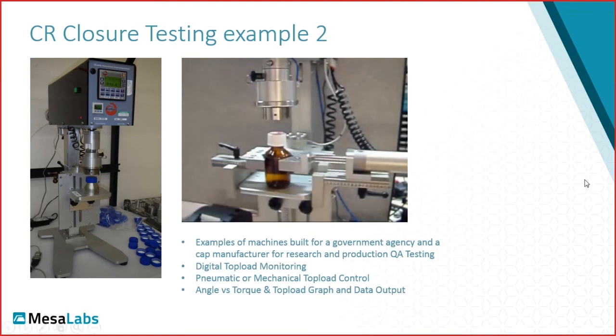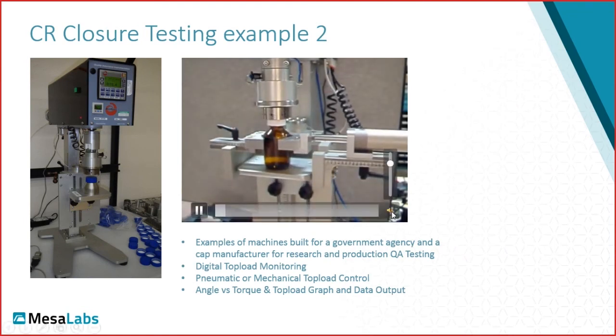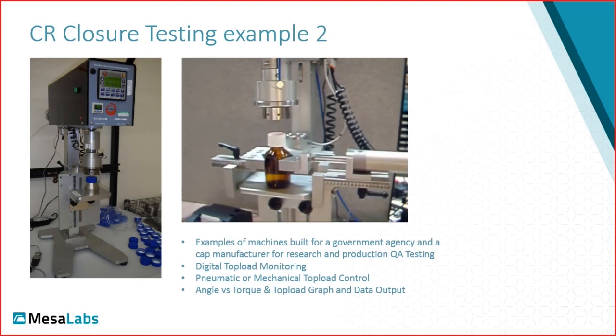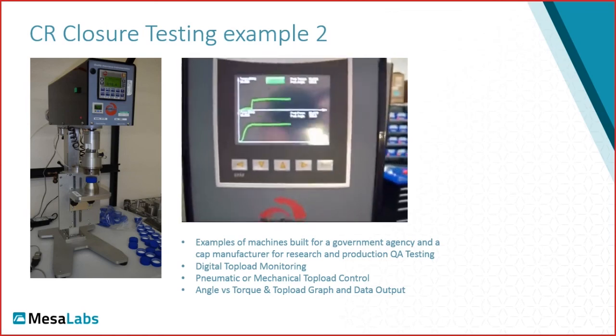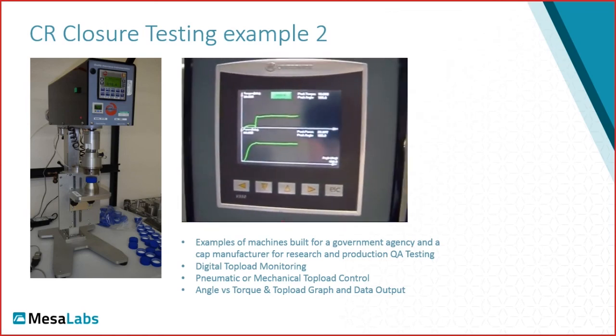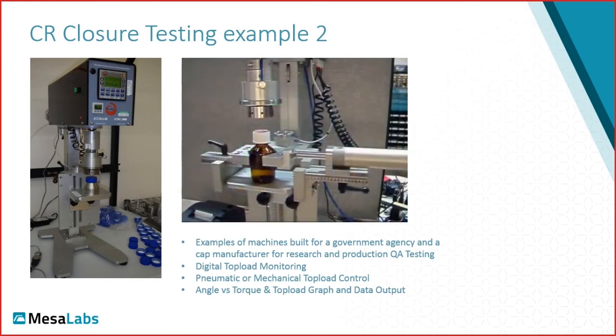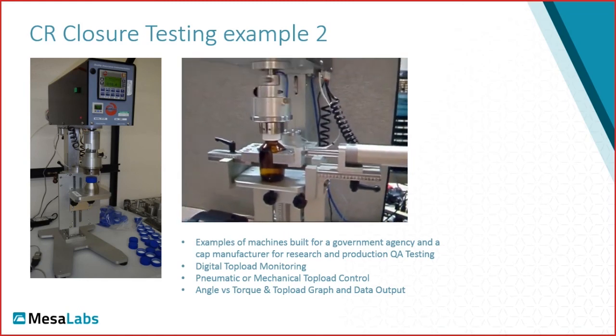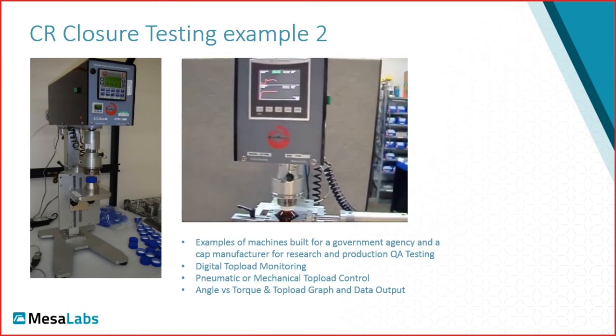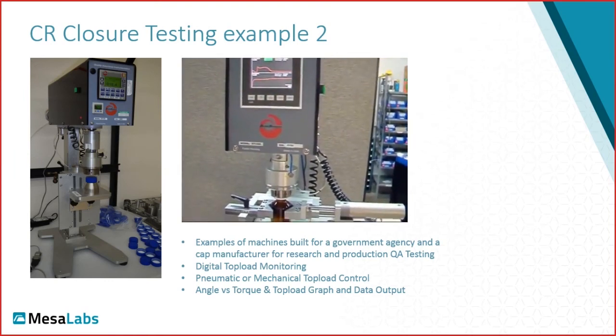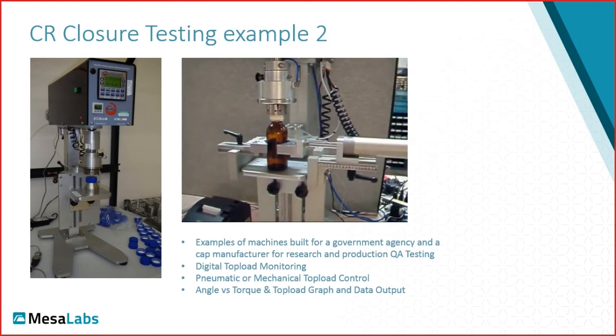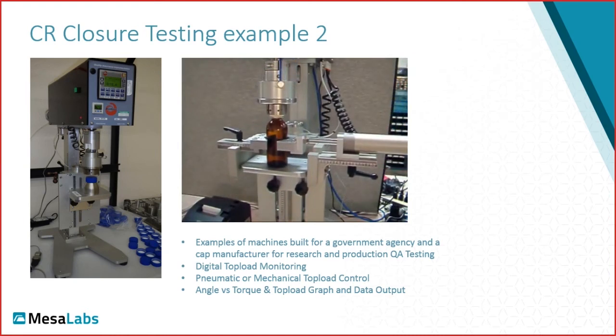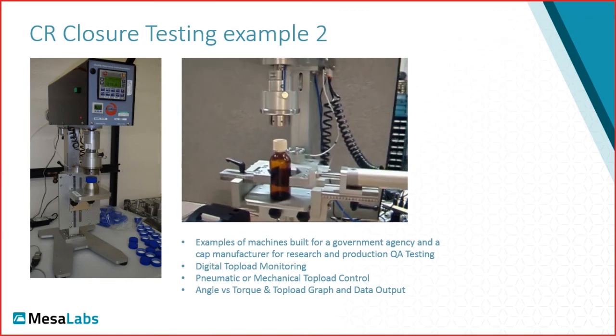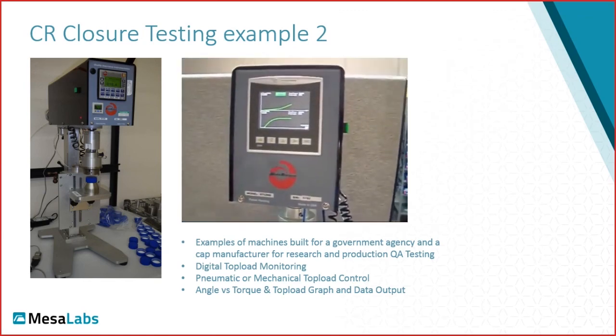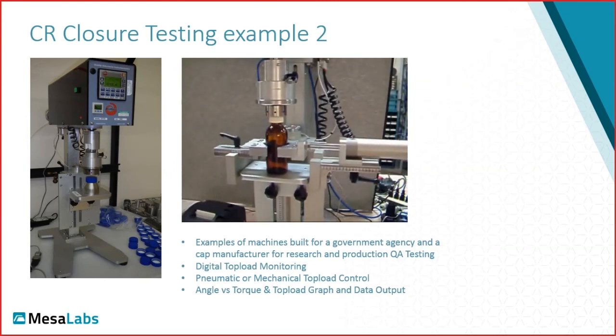The second example here, I believe this machine we built for the US CPSC, and this was allowing them to measure removal torque on child-resistant closures. The screen design is very similar, but here the operation is completely automated. So it includes digital top load monitoring, pneumatic actuated top load, and we are measuring angle and torque and displaying both the torque and top load on a chart, and the machine is also outputting that data to a computer.